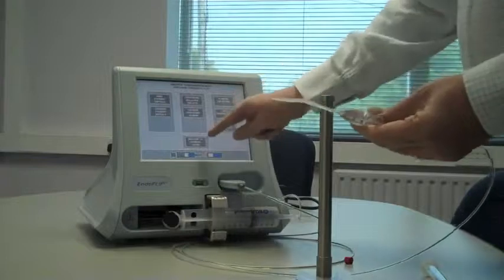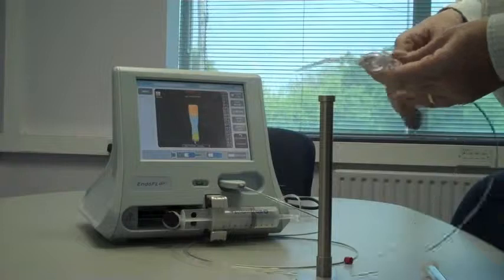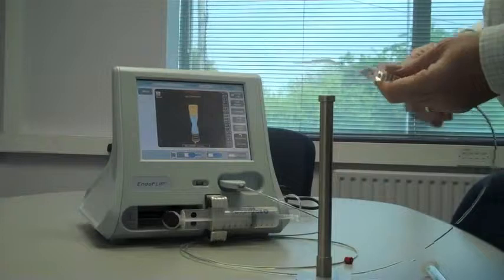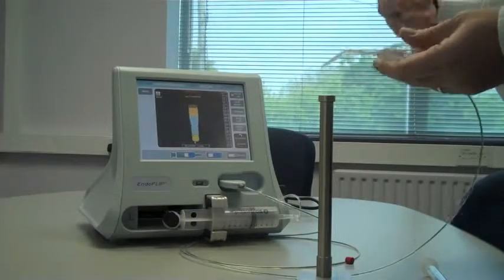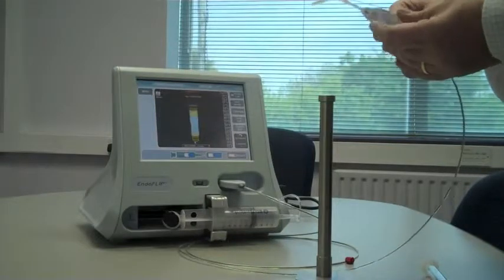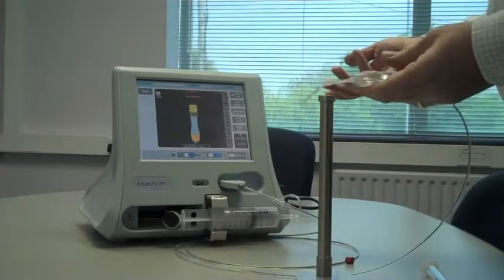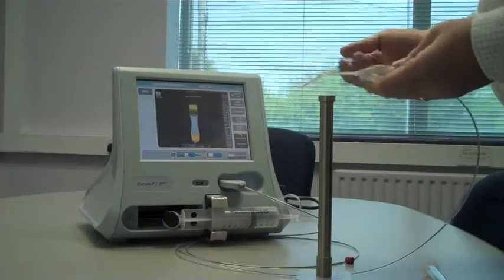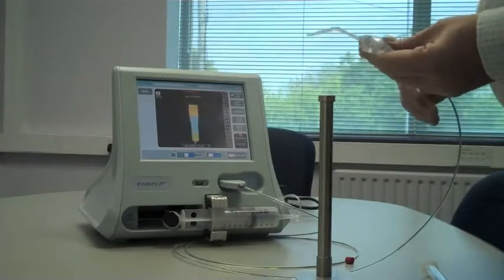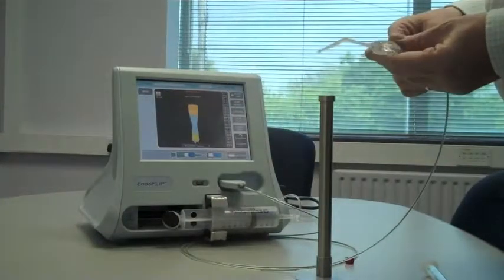So that's it. It's a fairly simple system to use. Return to normal mode. It measures dimensions, and it can measure volume and give you the minimum cross-sectional area as well. In other educational materials, we'll talk about the use of some of those figures, but certainly from a surgical standpoint, generally the main interest is an actual stoma size, for instance in a bariatric revision, or a band stoma size to allow intraoperative band adjustment, or finally to allow a sleeve size to be measured as you're creating the sleeve.